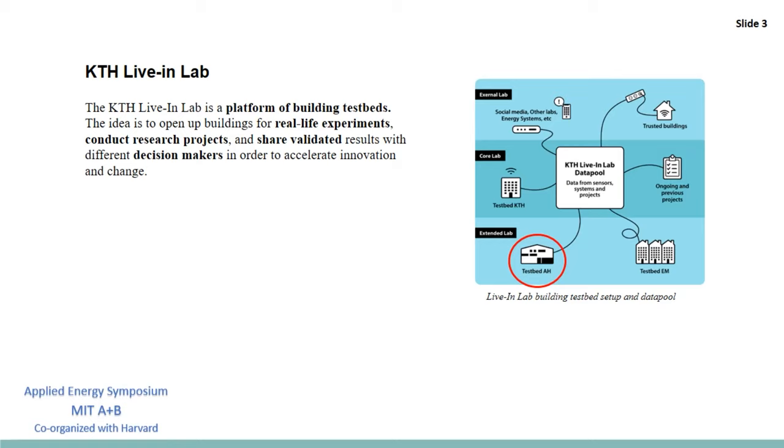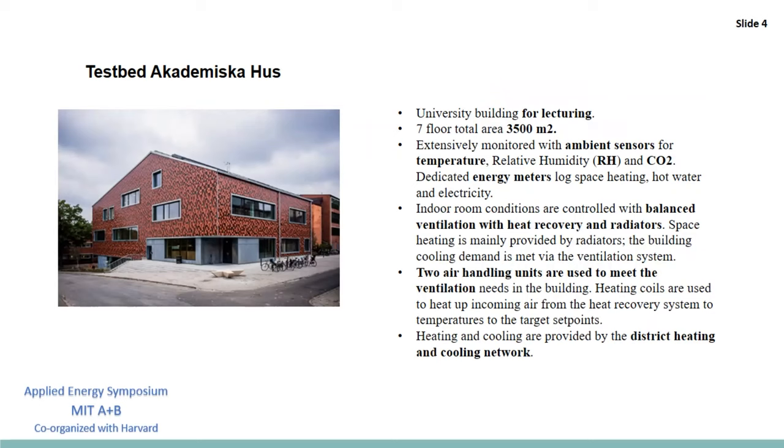The testbed object of this presentation is Testbed AH which stands for Akademiska Hus. This is part of the so-called extended testbeds which includes buildings typically equipped with modern but standard equipment. Testbed Akademiska Hus is a university building for lecturing with seven floors and an area of 3500 square meters. It has an extensive monitoring system to monitor temperature, relative humidity and CO2 concentration and dedicated energy meters for energy monitoring. Indoor conditions are controlled with balanced ventilation with heat recovery and radiators. The ventilation is supplied by two air handling units equipped with heating and cooling coils. Heating and cooling are supplied by the district heating networks.